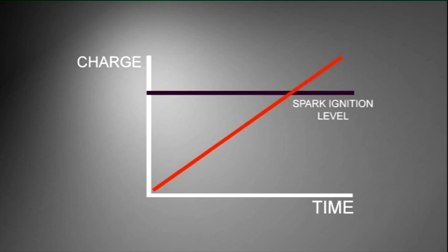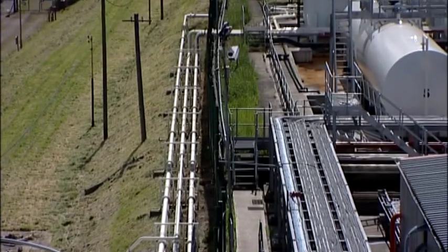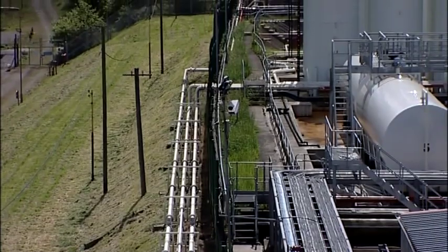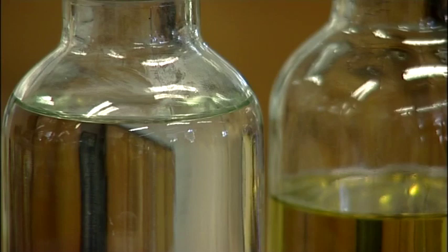The slower the rate of charge generation, the more chance it has to dissipate and avoid reaching the level of charge sufficient to cause an igniting spark. The generation of static electricity cannot be eliminated, but its rate of accumulation should be minimized, although this is not always possible for some end uses of solvents such as spray applications. In pipes, there are recommended safe maximum velocities for hydrocarbon solvents for various pipe diameters, but there are exceptions for particular solvents and for the presence of contaminants.